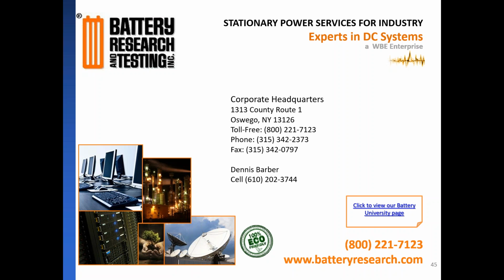I'm sure you guys do this for your customers at a certain frequency. We do. Load testing is probably 20% of our business. We get contracted even by other maintenance companies. They'll come in with something suspect and want something qualified. Or it's actually getting to be more of a common practice for commissioning or acceptance testing of a new installation. When we capacity test a battery on a new installation, we'll also utilize the load banks on the rectifiers and put the rectifiers in current limit, and we utilize them for thermography.